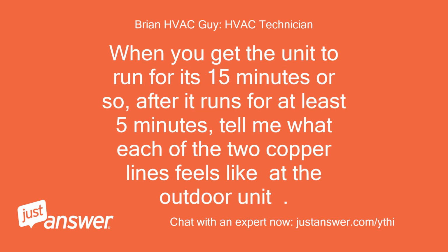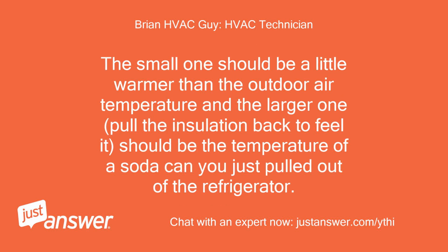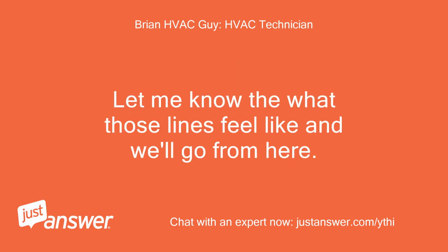When you get the unit to run for its 15 minutes or so, after it runs for at least 5 minutes, tell me what each of the two copper lines feels like at the outdoor unit. The small one should be a little warmer than the outdoor air temperature, and the larger one, pull the insulation back to feel it, should be the temperature of a soda can you just pulled out of the refrigerator. Let me know what those lines feel like and we'll go from here.